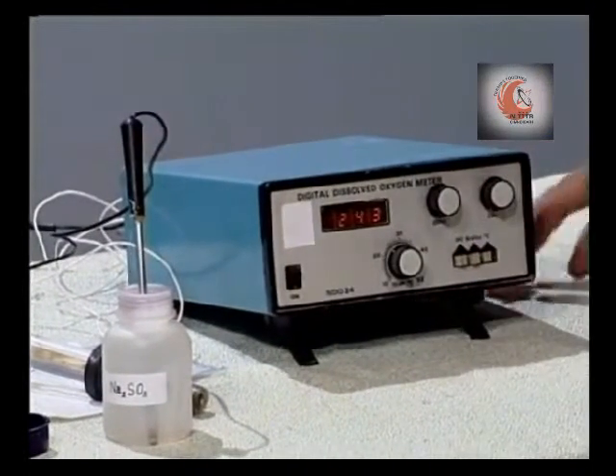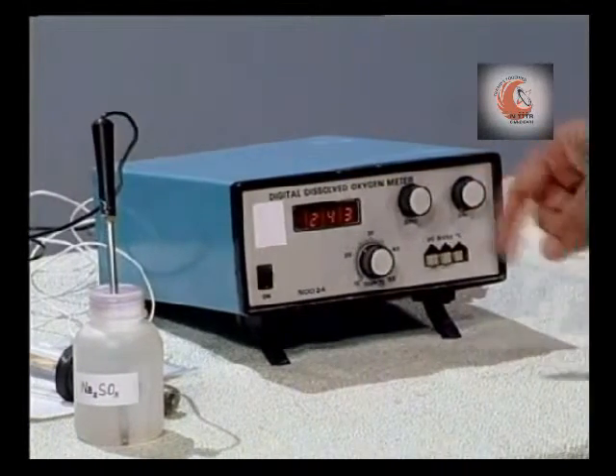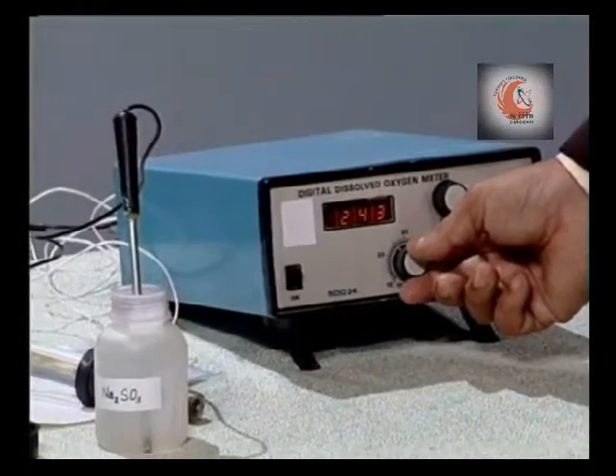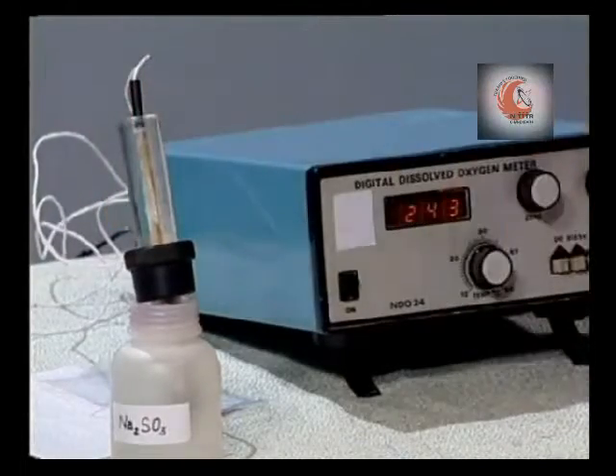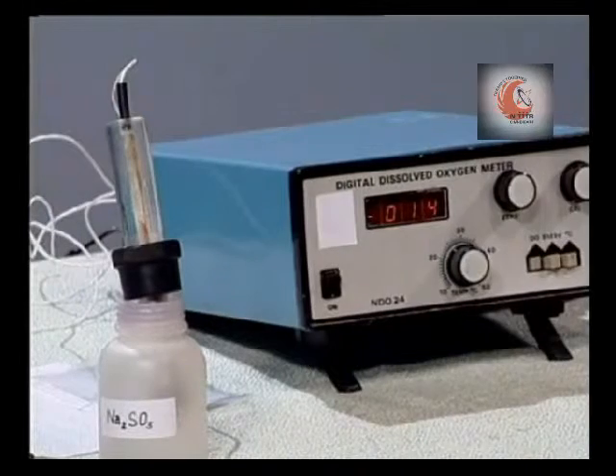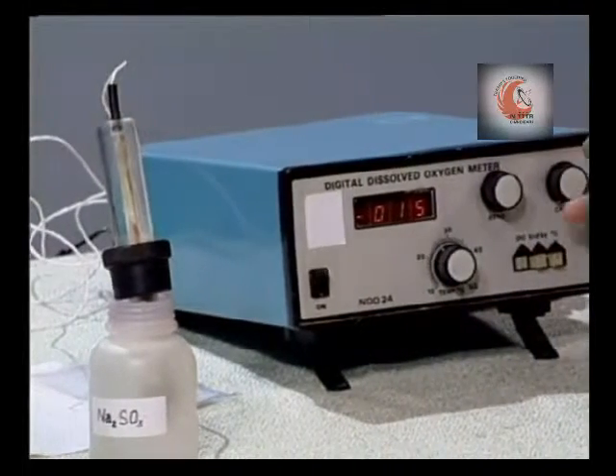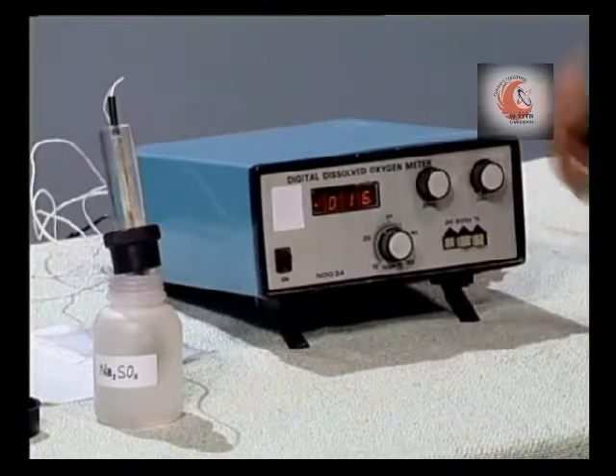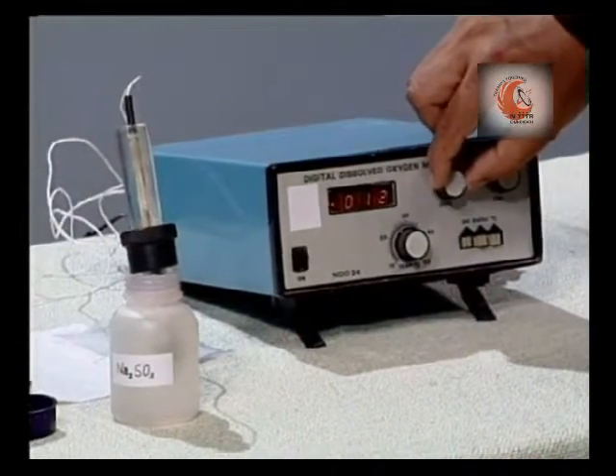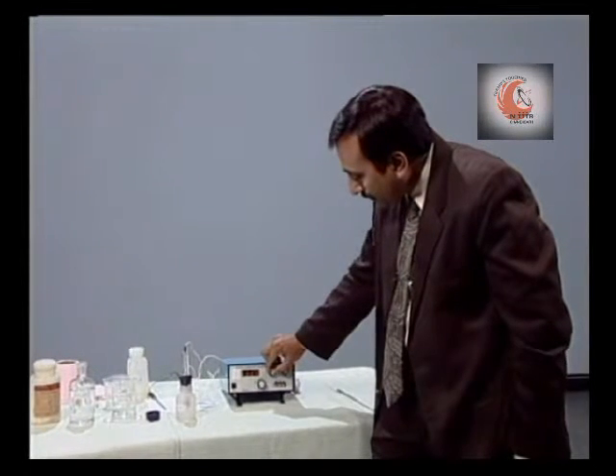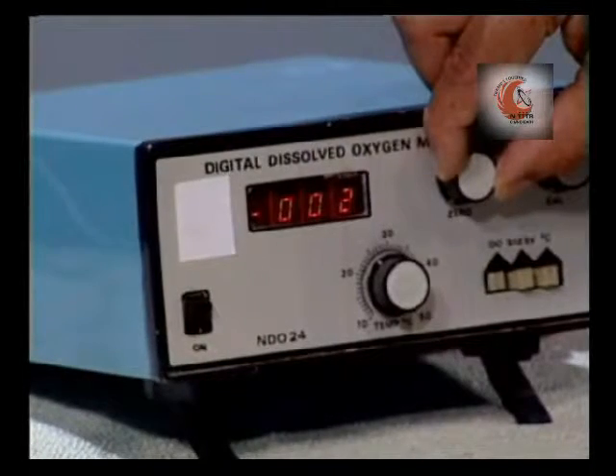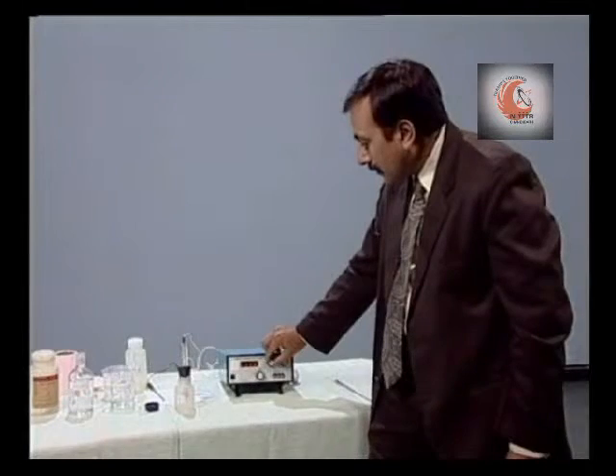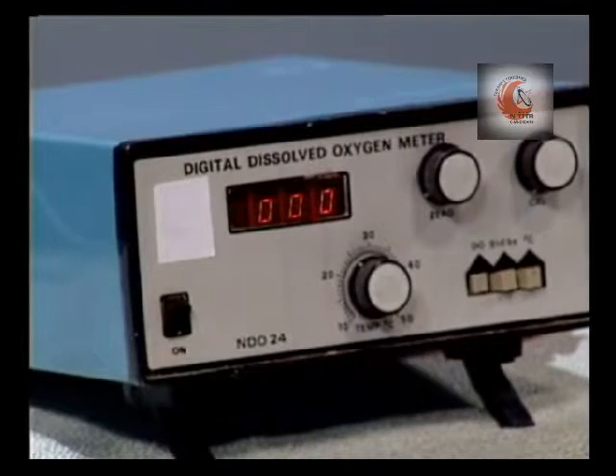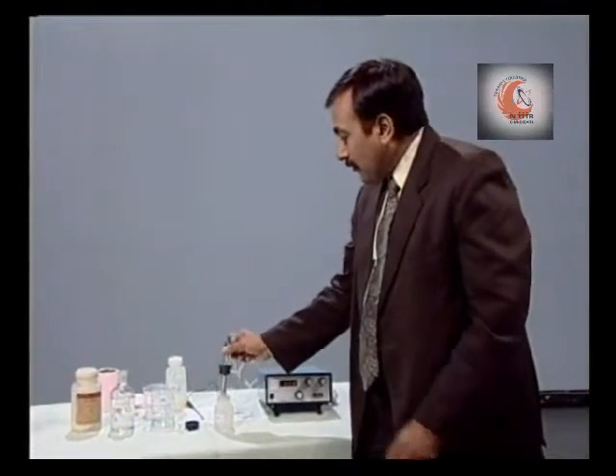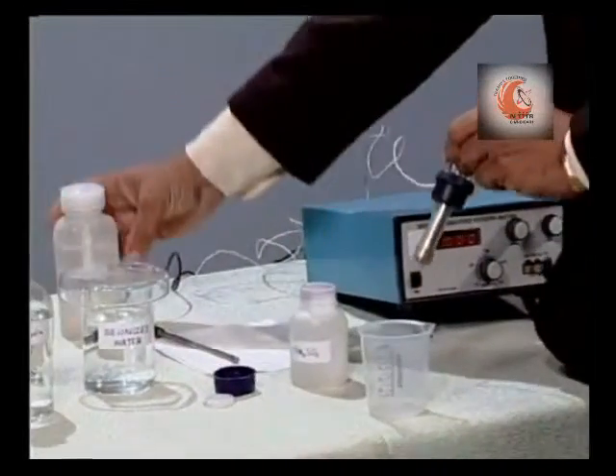Now, first we will measure the temperature. The temperature is 24.3, so keep the temperature knob against 24.3. Now, when we do the zero calibration, the cal knob should be on extreme left position. Now, adjust the meter reading with the 0 set knob, so that the display is 0 0. Now, take out the probe and wash it with distilled water.